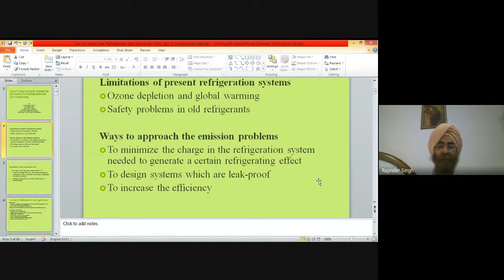Now, as I explained, when we use water in our central air conditioning plant as a secondary refrigerant, this water application is only limited to air conditioning. But why can't we do this for refrigeration purposes? In refrigeration, if we want to use water as a secondary refrigerant, below 0 degrees water starts freezing. So we cannot use water as a secondary refrigerant in our refrigeration system. That is the limitation, it works only for air conditioning systems.